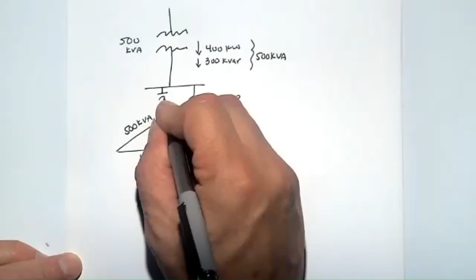We want to apply a capacitor to relieve some of the capacity of that transformer so that I can add another load over here. I can put some other load, whether it's resistive or reactive or a combination of loads. So let's say the target power factor is 0.95. How do I get there? So my target power factor is 0.95.